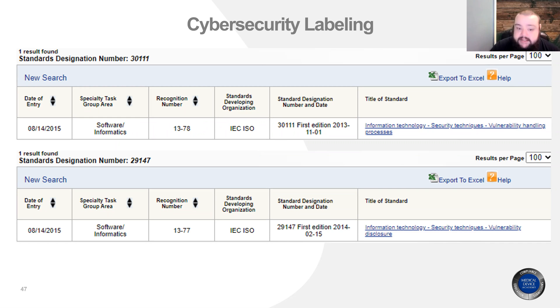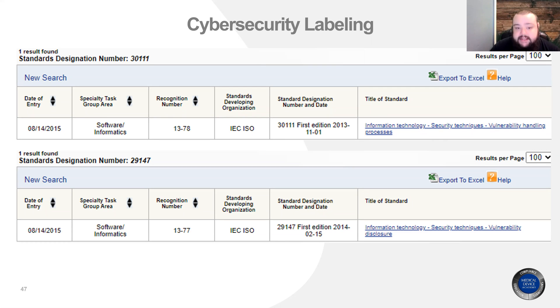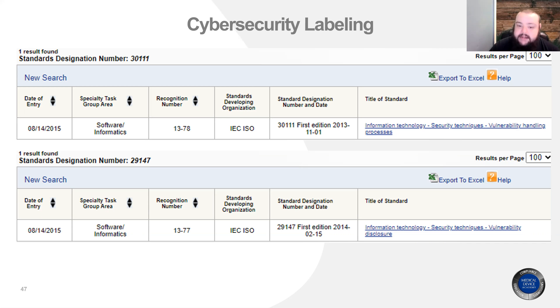The reason I emphasized the second edition and date revisions of those standards is that the FDA's recognized standards list shows the FDA still currently recognizes the first editions — the 2013 and 2014 editions — of those standards. So you have to juggle regulatory compliance, where the FDA recognizes the first edition, with the understanding that the second edition is the accepted state-of-the-art standard, and do your best to blend the two together.